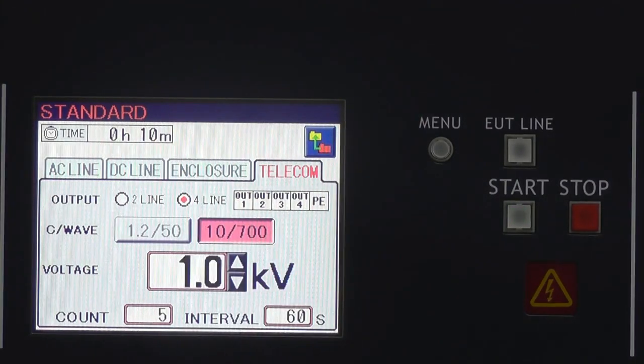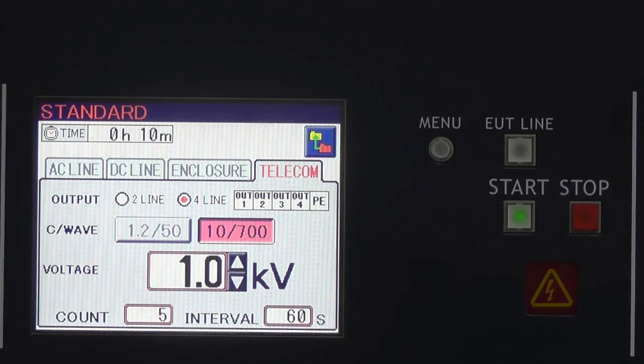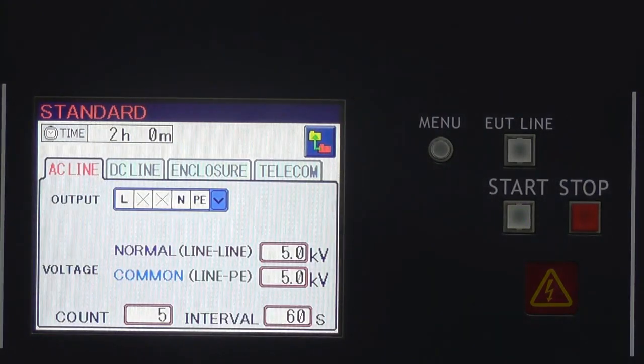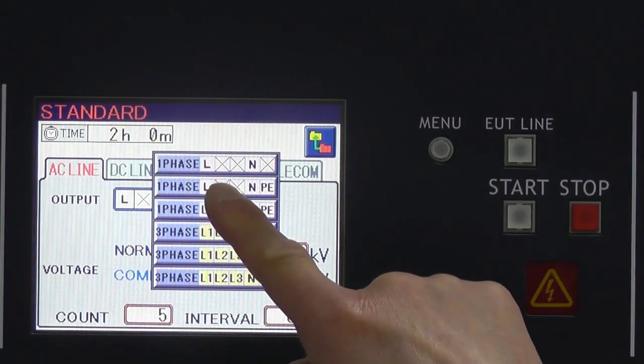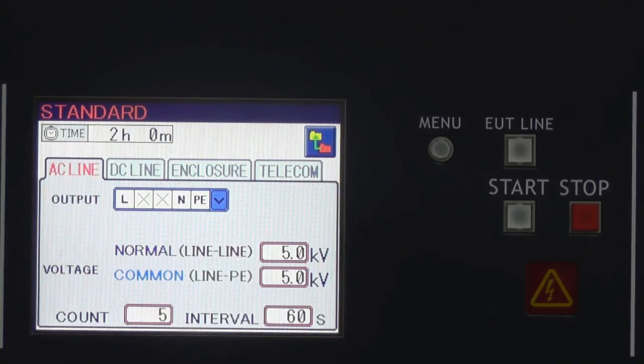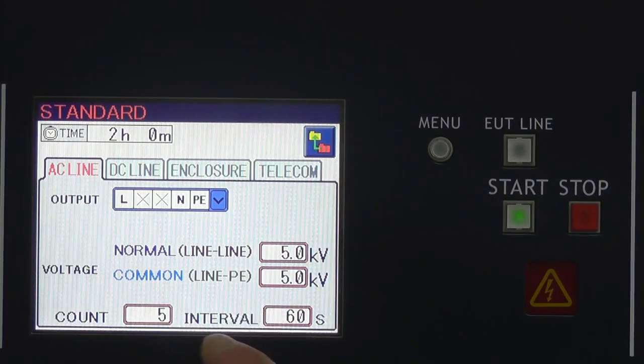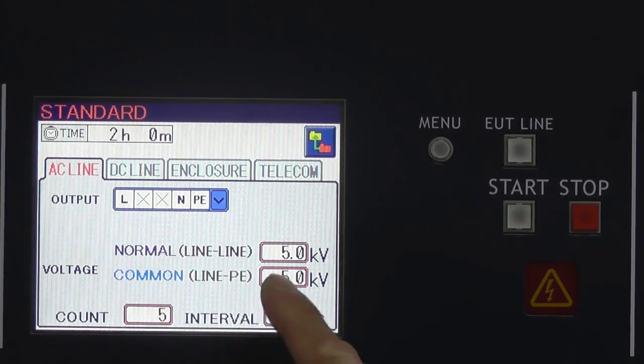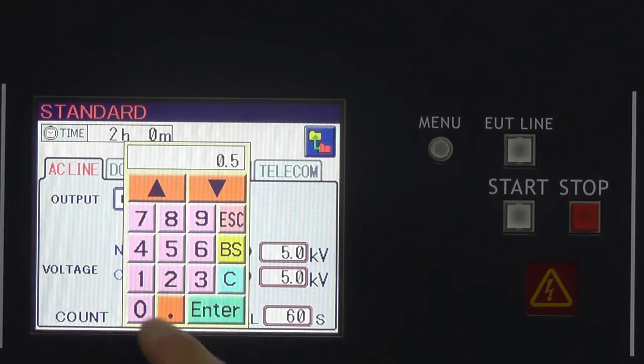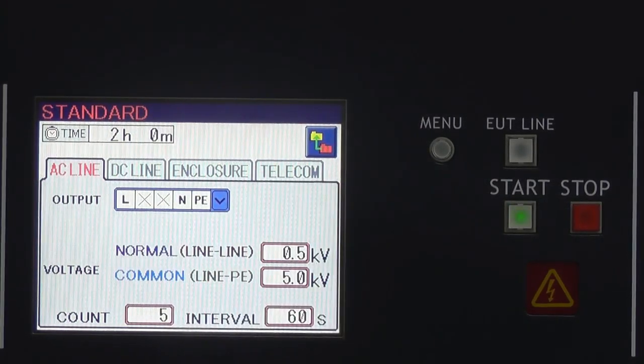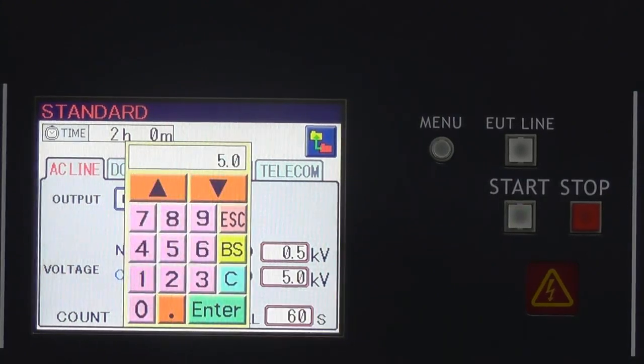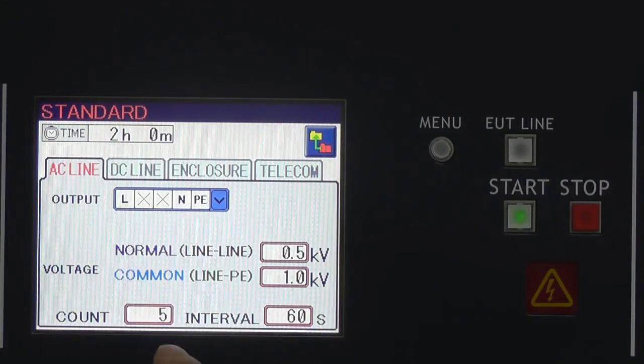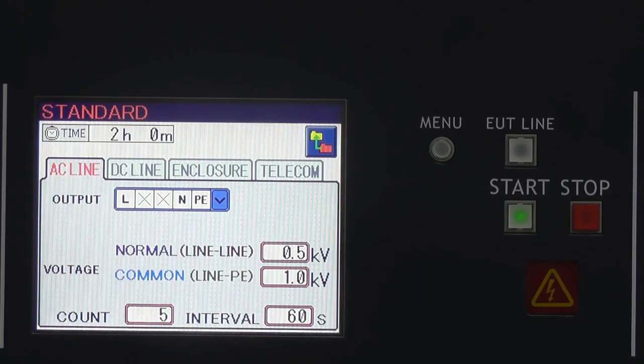Okay, here it shows the test time of 10 minutes. That means it requires 10 minutes to complete the testing we just set. Okay, let's go back to the AC line make example. If we want to do the simple line test, a single line test, we set the voltage for normal mode and common mode. For example, we set normal mode at 0.5 kV and common mode 1 kV, and count 5 and interval 60 seconds.